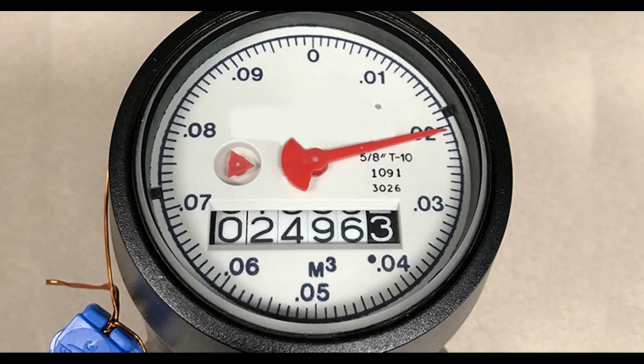Water meters do not distinguish between air and water, both are counted as fluid. There are two regulations that water companies and meter manufacturers do not comply with, and they charge air for water. A measuring system shall be equipped with an effective air/vapor eliminator or other automatic means to prevent the passage of air/vapor through the meter. Ref. Handbook 44 to 2019 3.30. S.2.1. Measuring systems shall incorporate a gas elimination device for the proper elimination of any air or undissolved gases which may be contained in the liquid before it enters the meter.